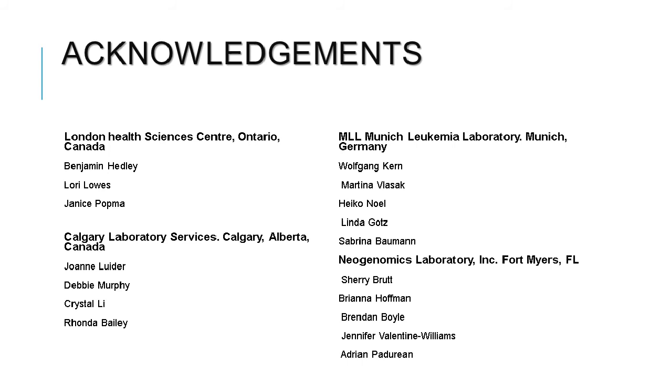How often do you really need to perform compensation or calibration on these systems? Because the reagents are lyophilized — dried down — they are very, very stable. The recommendation is to do compensation once a month. You can extend that by just checking the compensation daily to make sure the beads are falling correctly, and unless there are any major changes to the instrument, that can probably be extended.